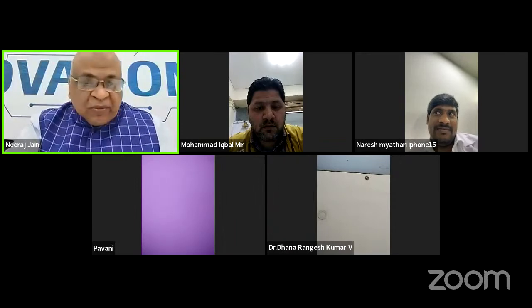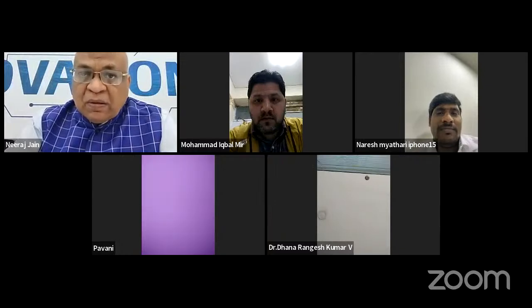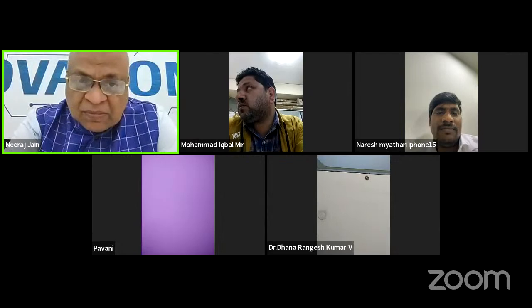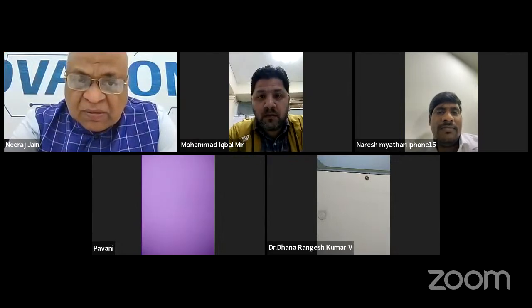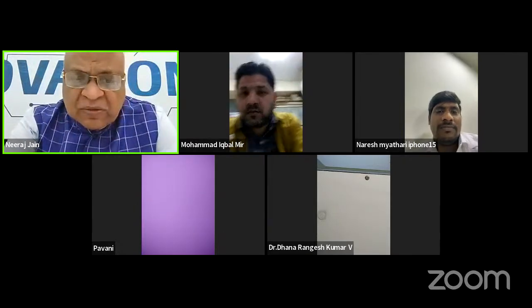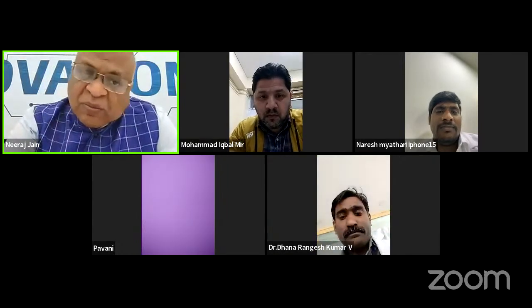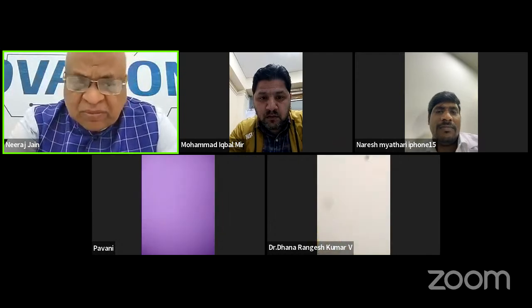Please read the question again, because I was not able to unmute, so I was concentrating on that. Why copy IFU information for use and put them as SOPs in our manuals? Instead, we can as well file the kit inserts. Yes, you can file the kit insert also, and whatever additional information you want to incorporate in that SOP, you can do that. That is also acceptable.